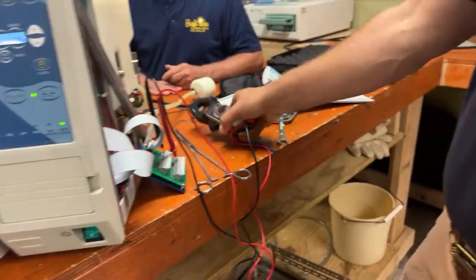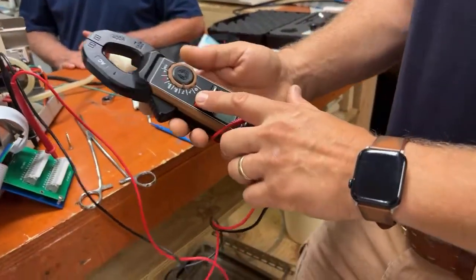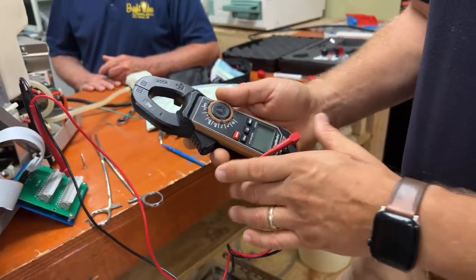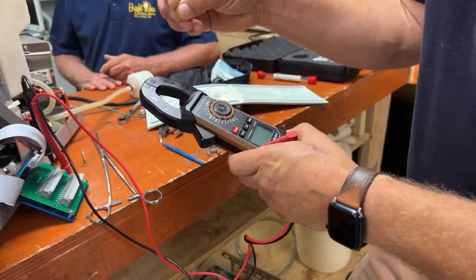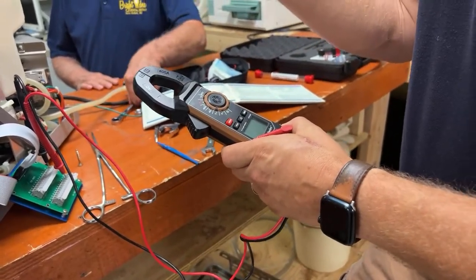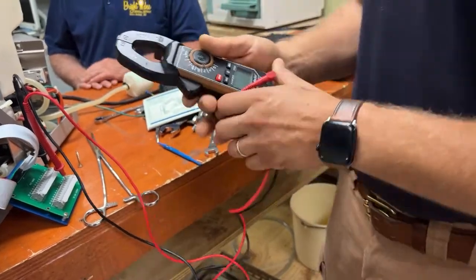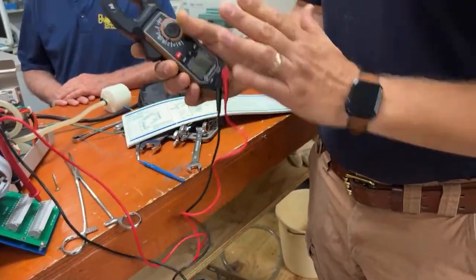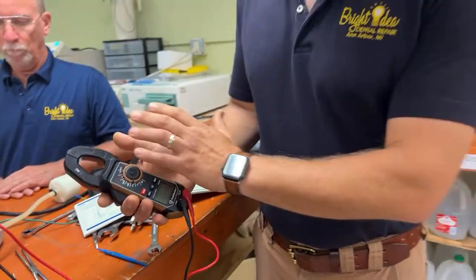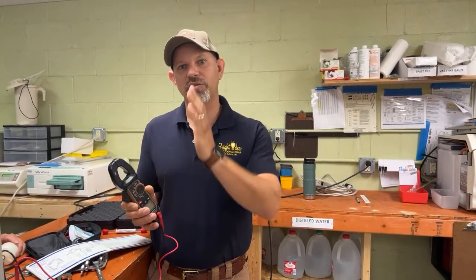I'll definitely say something about test equipment. If you ever are using a multimeter, it's important for you to understand what reading you're expecting to get. And if you're not actually getting that reading, it's always important for you to check your equipment. I think probably about half the time, I might not have a good connection, or I might not have something hooked up in the right spot. So before you just automatically jump to there being a problem in the machine, you always want to check your test equipment.